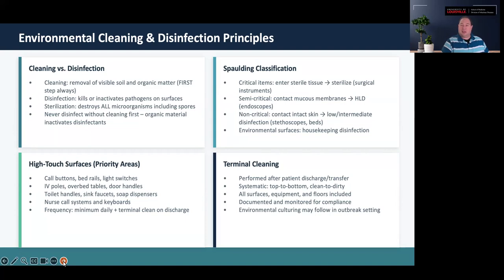The other thing, just as an aside, is if you ever see high-level disinfection done in the outpatient setting, you should run, because that is not something that we routinely want to see done. It's just not a safe practice. We're not set up to do that in the outpatient setting. So ideally, if it's going to be done, it should be done in the hospital and the SPD department where you've got properly trained people and the right equipment.